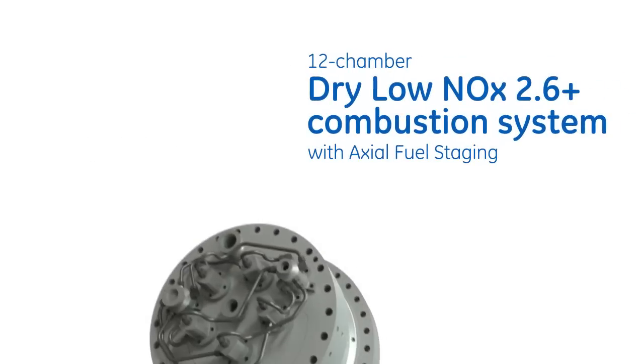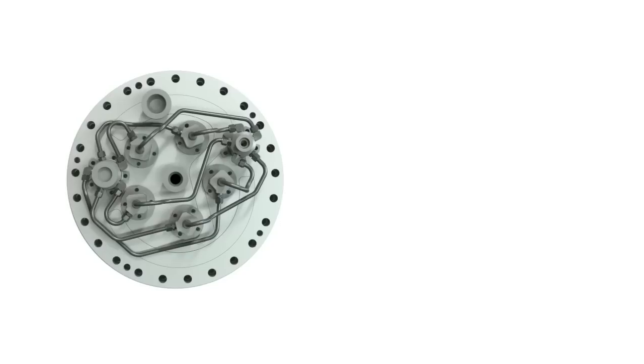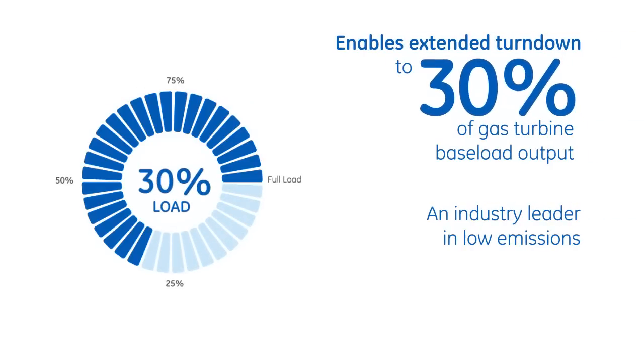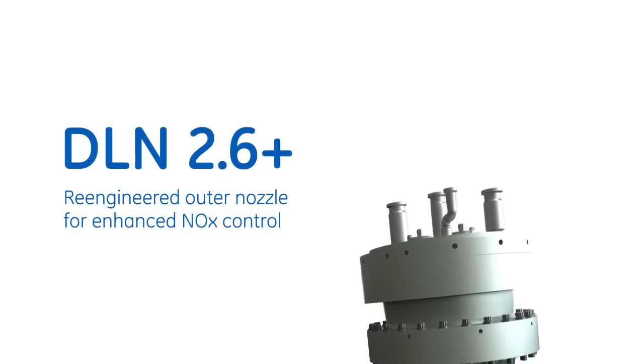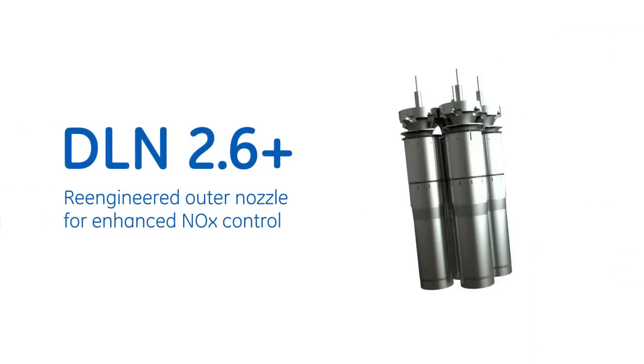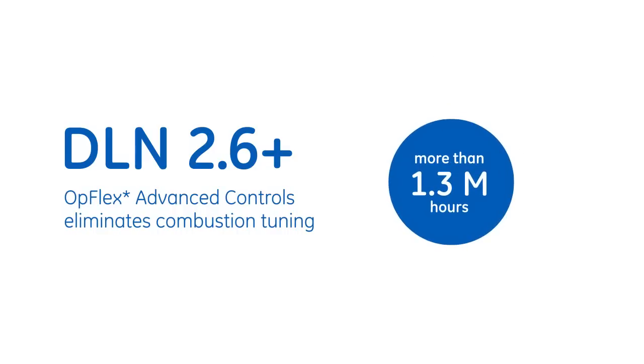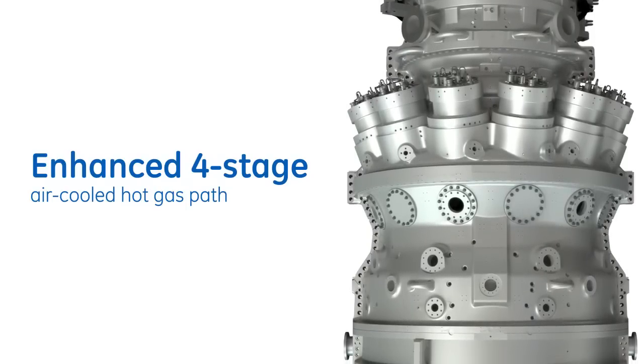The next evolution of combustor technology, the dry low-NOx DLN 2.6 Plus with axial fuel staging, enables extended turndown as low as 30% of base load within emissions compliance, while accommodating a fuel composition variance of greater than 15% modified Wobbe index. The DLN 2.6 Plus features a central premix nozzle and five outer nozzles which have been re-engineered, adding a fuel passage upstream of the nozzle and swirler, and eliminating the diffusion passage.